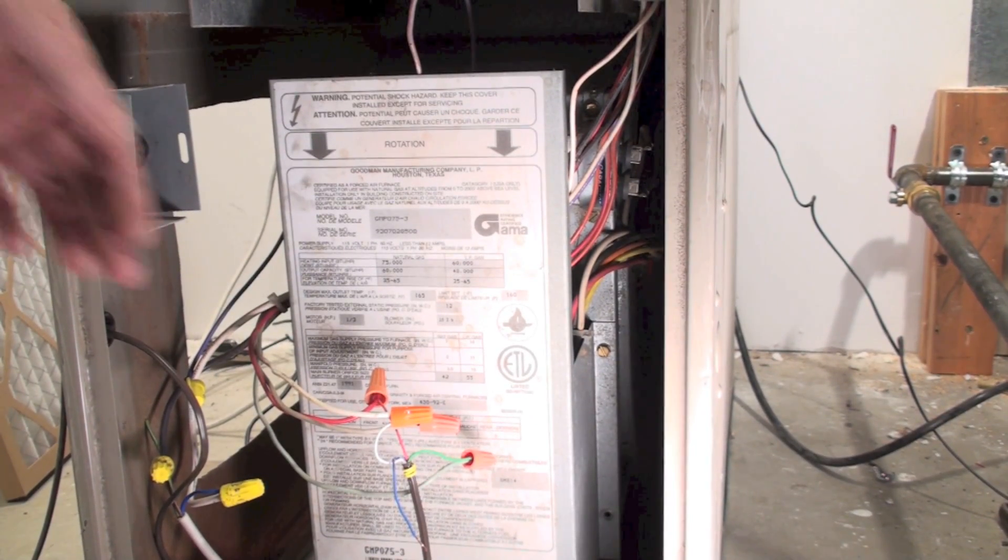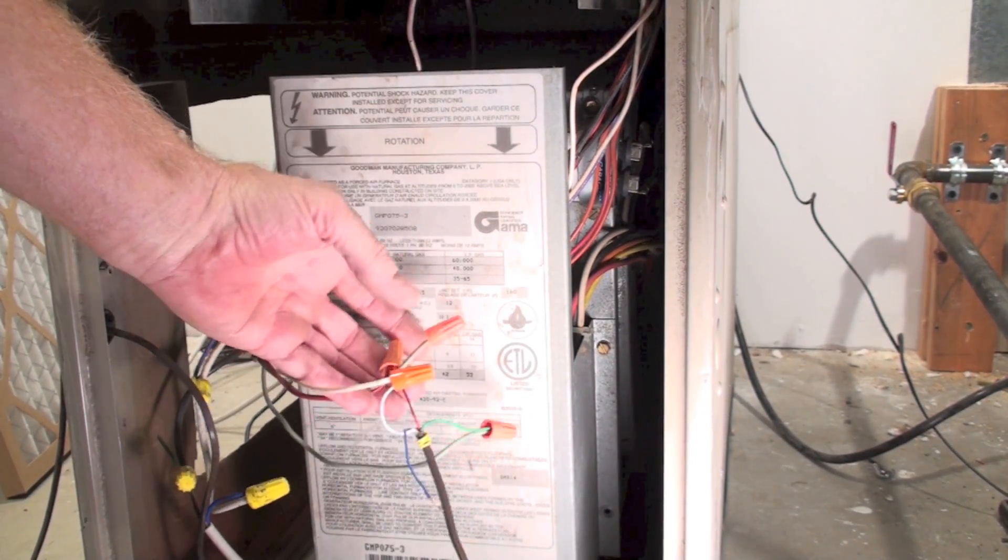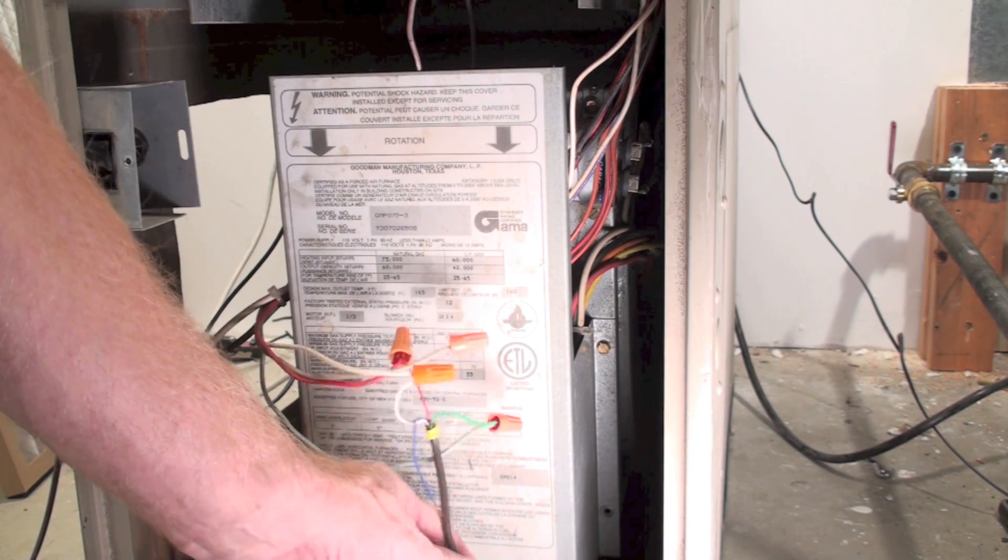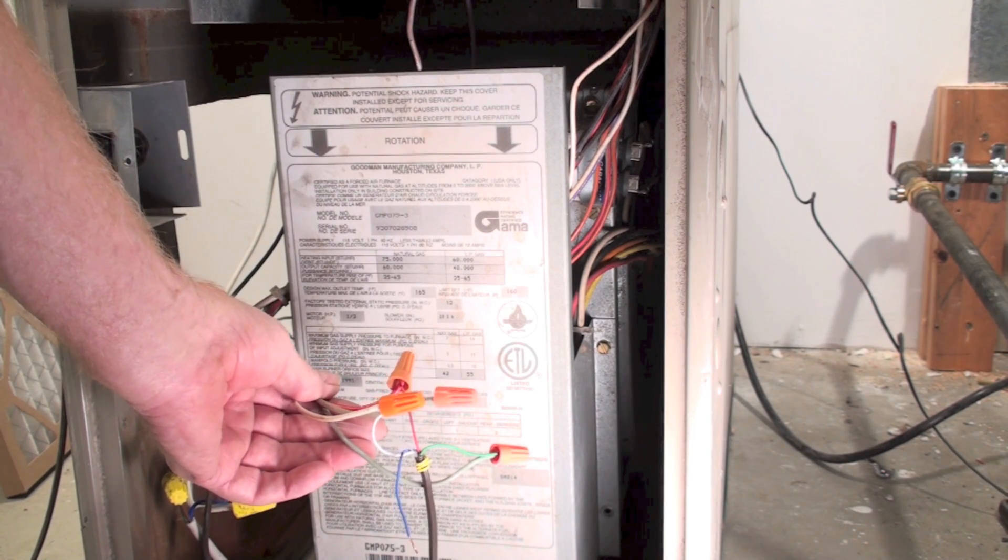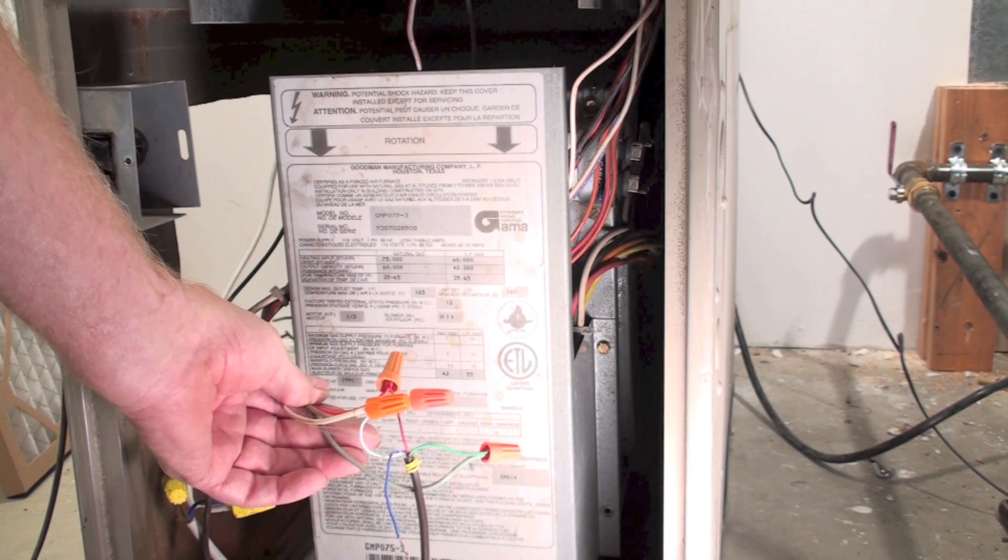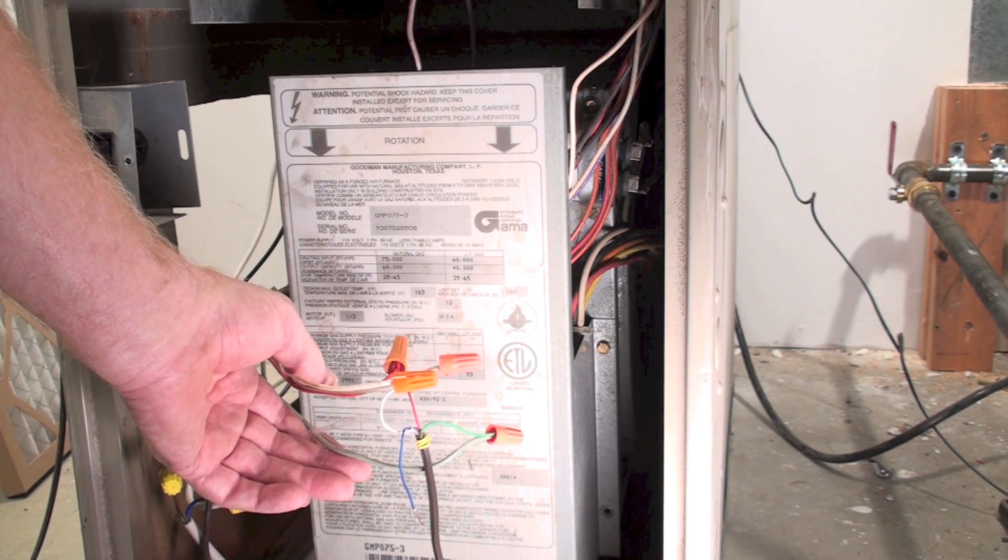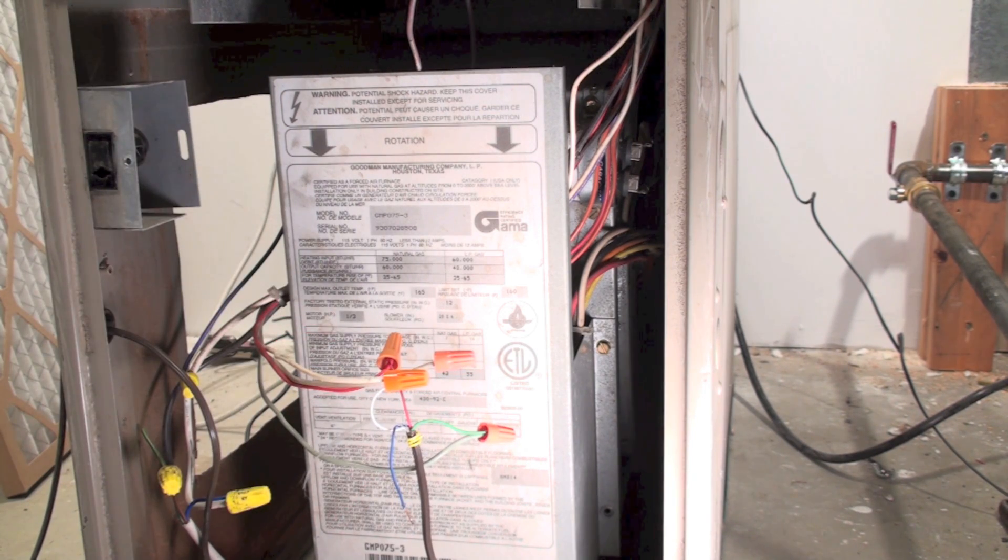Now this one simply has wire nuts, wire nutting the low voltage wires together. Here's your low voltage wire going up to the thermostat, and these are the wires coming out of the control. Now, if I want to find out where to set the anticipator on this, I have to determine the amperage draw of the control circuit.